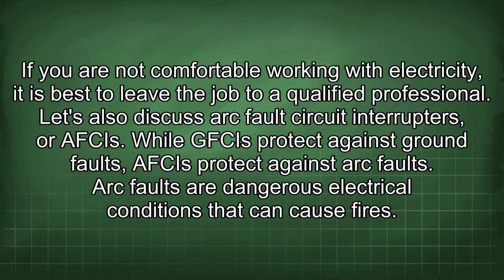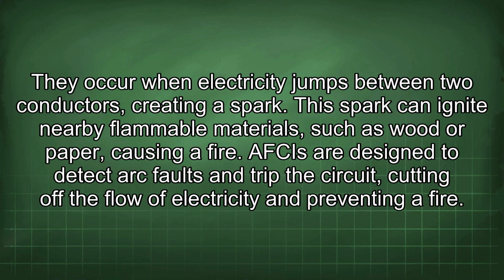Let's also discuss arc fault circuit interrupters, or AFCIs. While GFCIs protect against ground faults, AFCIs protect against arc faults. Arc faults are dangerous electrical conditions that can cause fires. They occur when electricity jumps between two conductors, creating a spark. This spark can ignite nearby flammable materials, such as wood or paper, causing a fire. AFCIs are designed to detect arc faults and trip the circuit, cutting off the flow of electricity and preventing a fire.